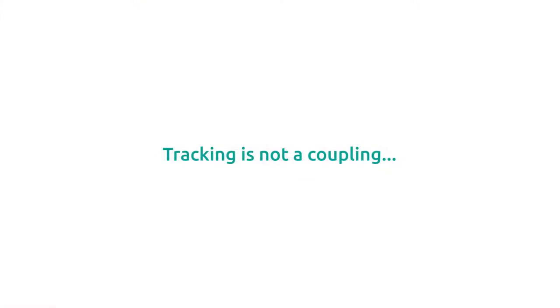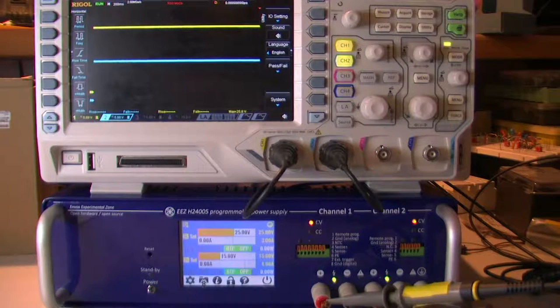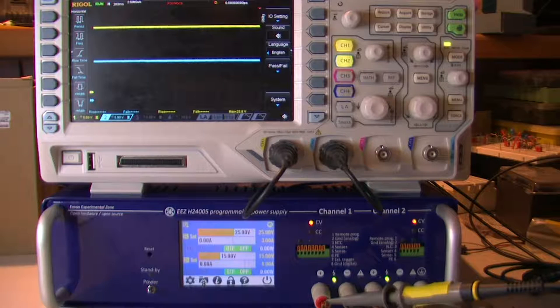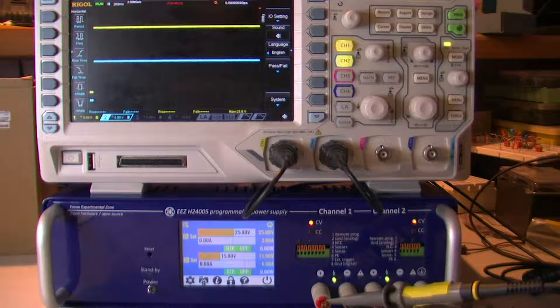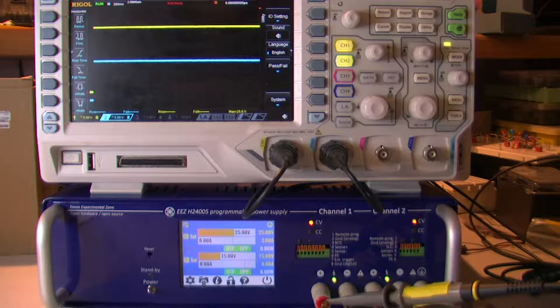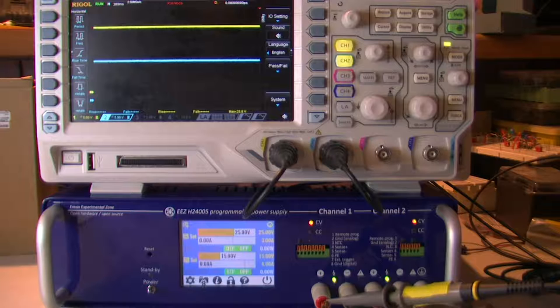In our case, tracking mode is used just for that, to control simultaneously both channel outputs, and it's not like with some other power supplies where tracking mode is used to simplify connection in series or parallel.